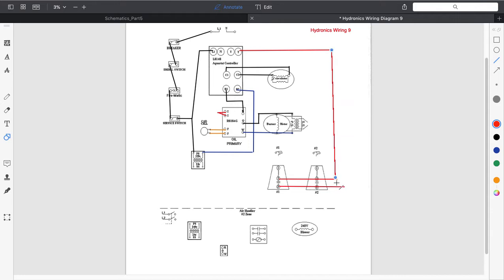Got to be careful with this, okay? Because you have pin 2, which is also going to be the common for the motor, for the zone valve motor side. I'm going to come out of this T. I'm going to come in there. And there's a reason I haven't tied in that neutral yet. We'll get to that in a minute. Just wanted to make sure I didn't jump in any wires. And we're going to connect that into there.